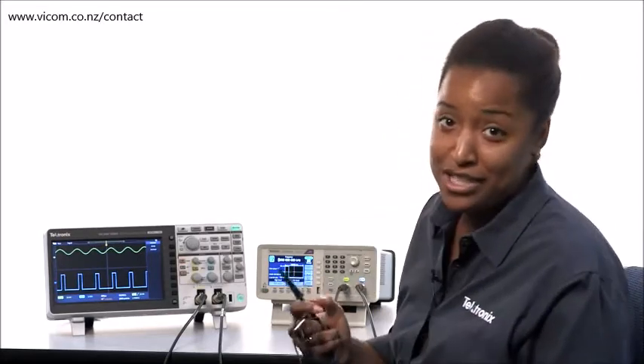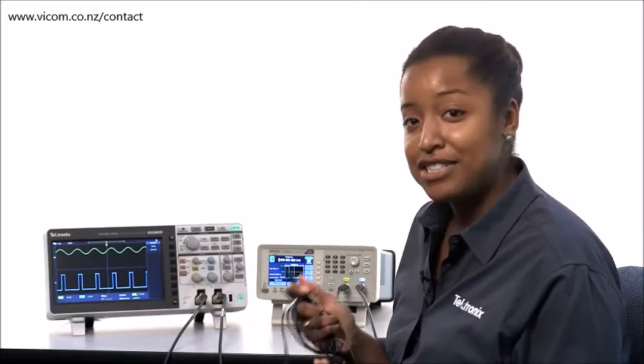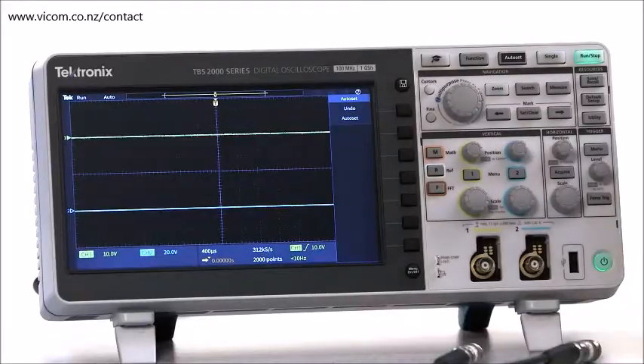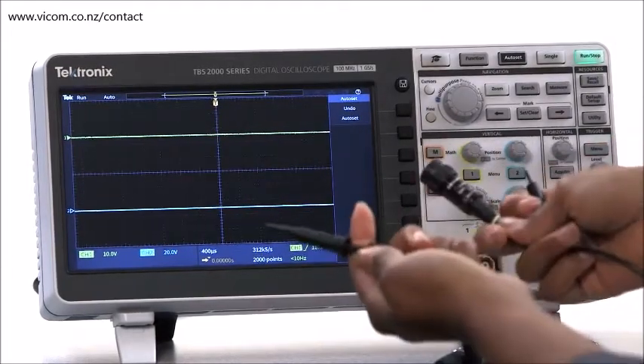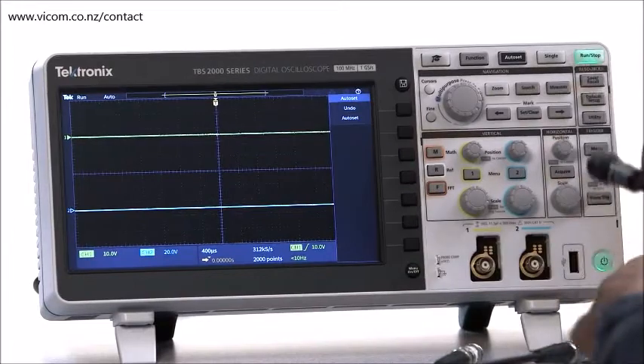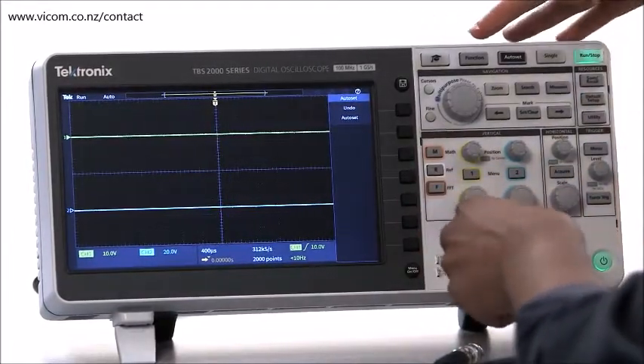Probes are often underappreciated. They're responsible for actually capturing the signal and impact all of what you see on the signal downstream. The most common probes divide or attenuate the input signal by 10. These are called 10x probes. They can measure relatively high frequency signals and have good voltage range.